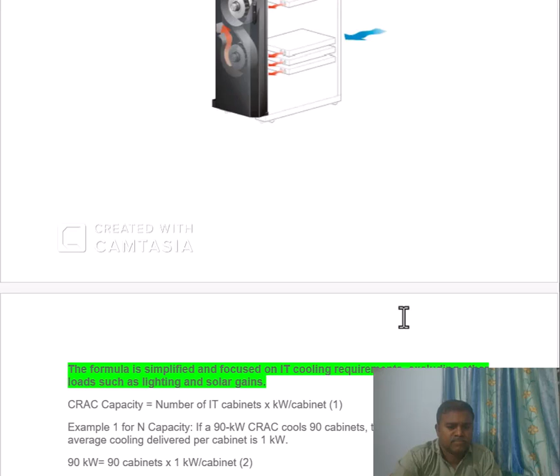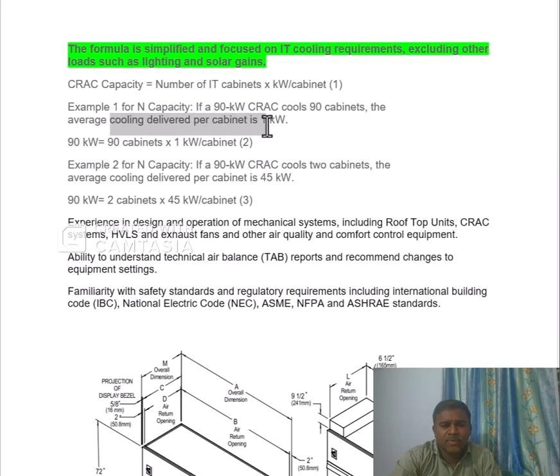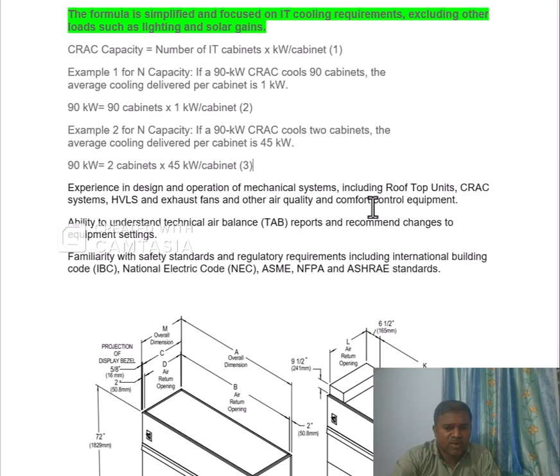This is one of the formulas you can use: CRAC units is equal to number of IT cabinets into kilowatt per cabinet. For example, if you have 90 kilowatt of CRAC cooling 90 cabinets, the average cooling delivered per cabinet is 1 kilowatt, since 90 is equal to 90 into 1 kilowatt per cabinet. Or if 90 kilowatt is cooling 2 cabinets, the average cooling delivered per cabinet will be 45 kilowatt, since 90 equals 2 into 45 kilowatt per cabinet. Depending on that, you can take the heat generated per cabinet and multiply to get the kilowatt, and from this you can size the equipment.